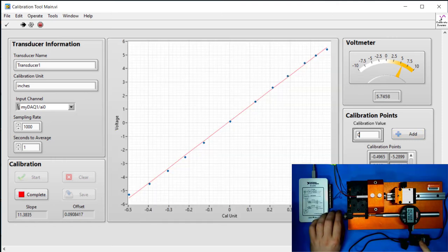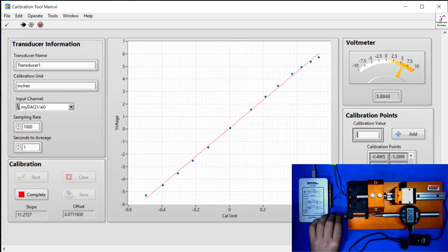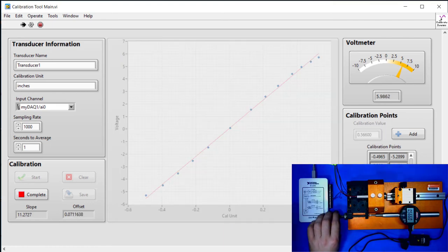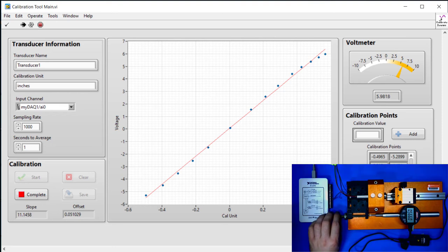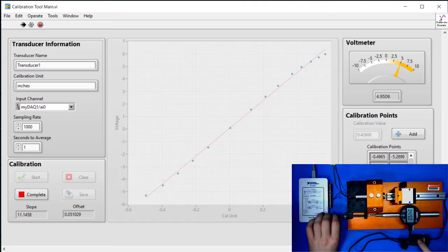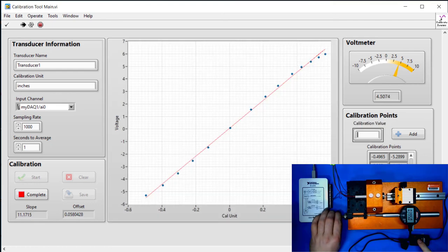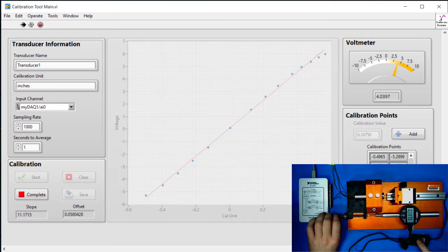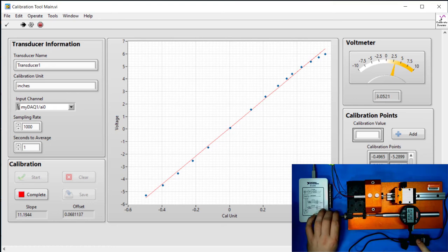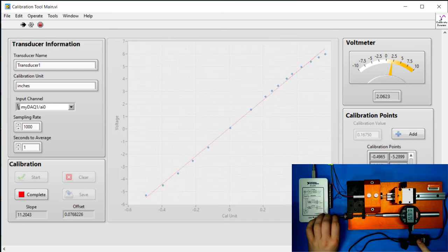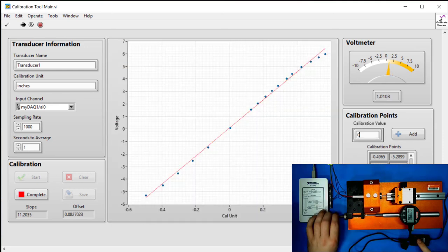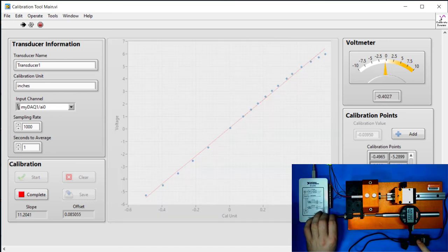And if we go off the ends of the transducer, I'll go a little bit past here, we can see that nonlinearity starting to creep in, so we know the exact range of this transducer. In fact, this transducer is slightly nonlinear on both ends. Now I'm going to come back down and add a few calibration points going in the other direction. And this just lets us know that we have no hysteresis in our sensor. You see they're falling very well in line in between the other calibration points.